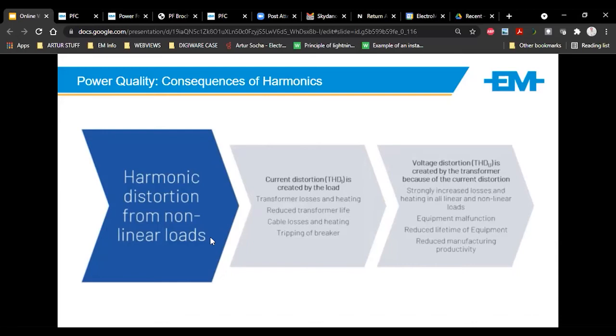What these harmonics can do is they can affect other equipment because, as I mentioned, the current harmonic results back as a voltage harmonic. Now that is seen by all the other equipment in the field. So a power supply might be seeing this. Another VSD might be seeing it. So there are ways to mitigate this. And as EM, we've got different solutions depending on what the problems are.